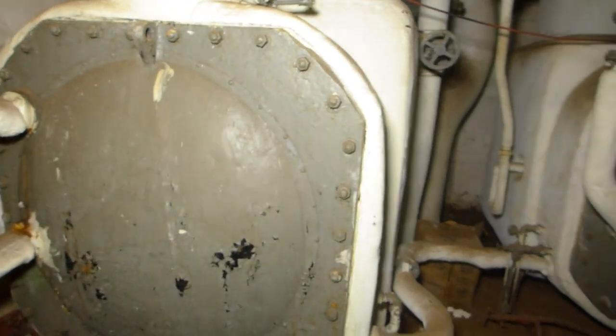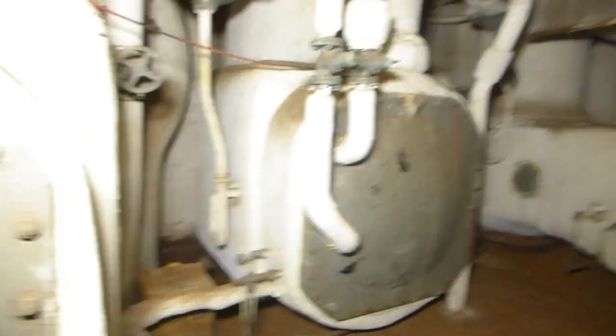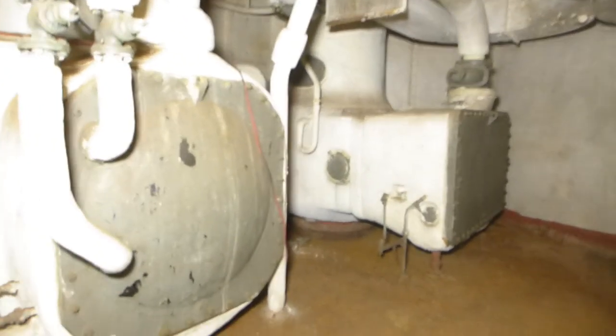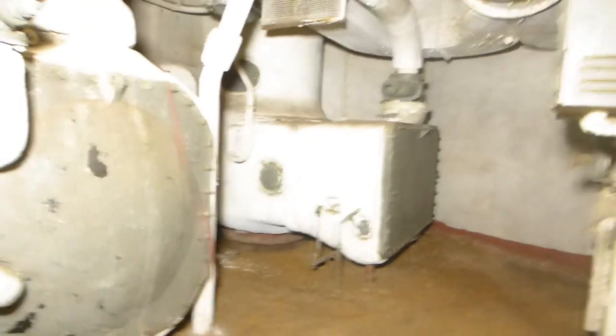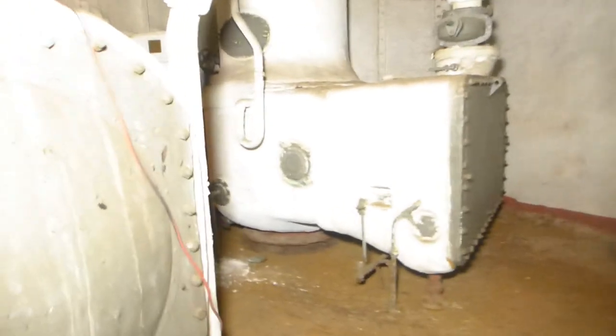Another thing is that because we're putting partial vacuums on all three of these stages, that lowers the boiling point, and even the highest temperature in that first effect is just low enough that it does not encourage buildup of calcium deposits or hard deposits on the heating tubes, which is a constant problem in boilers and in distillers.